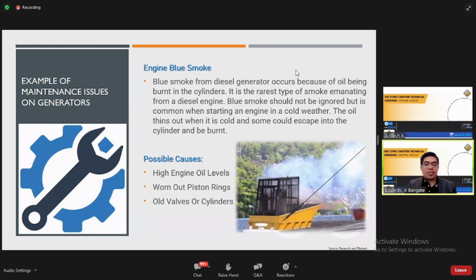Have you ever seen an engine with blue smoke? Blue smoke from a diesel generator is very rare, actually, because it is caused by oil being burnt in the cylinders. Okay? It is the rarest type of smoke emanating from a diesel engine. Blue smoke should not be ignored, but it is common when starting an engine in cold weather. Why? Because the oil thins out when it is cold and some could escape into the cylinder and burn. Possible causes: high engine oil levels, worn out piston rings, old valves or cylinders. So these are the checkpoints.